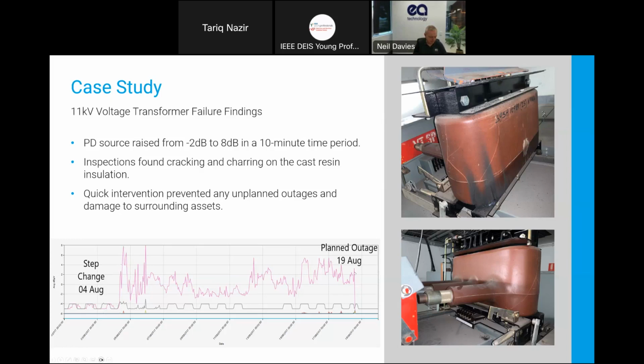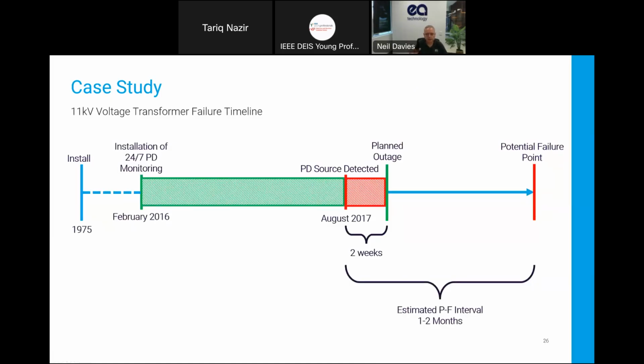Now, the outage was planned, but it was planned for a couple of weeks later, on the 19th. And when it was taken out of service, you can see we've got major sooting, burning on the VT. We've got big cracks in the insulation here. So we're going to be relatively close to disruptive failure occurring at this point. Let's think about that in terms of our timelines. We started the monitoring in February 16, and we've got the defect detected in August 17. And the switchgear is obviously there since 75. And 2 weeks later, we've got it in that state.